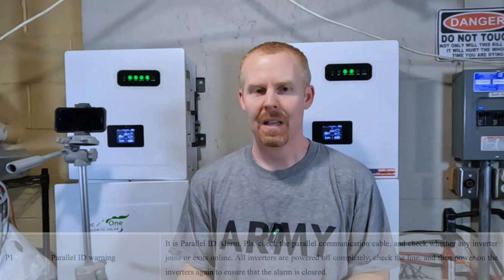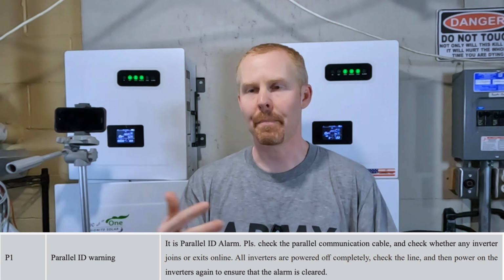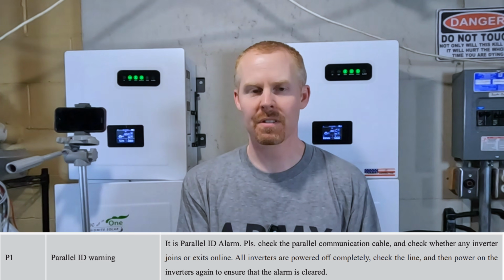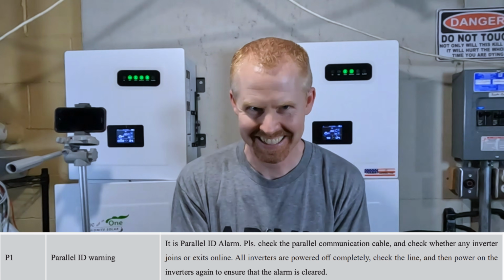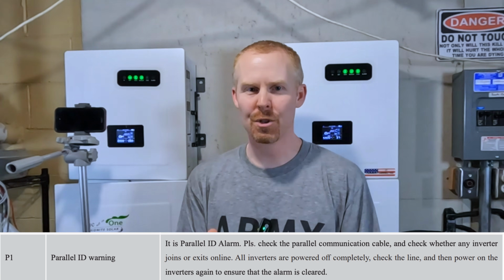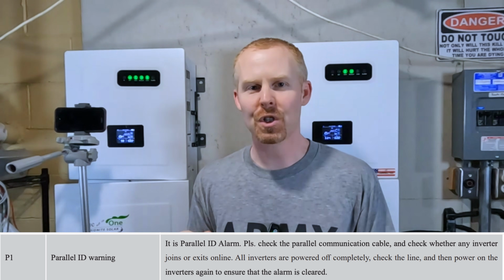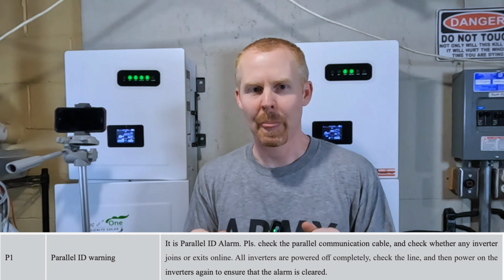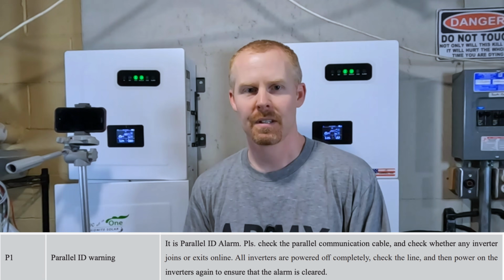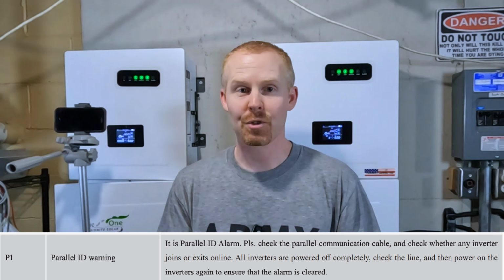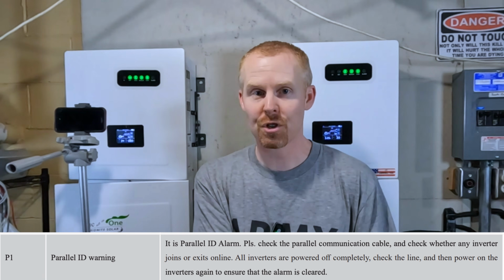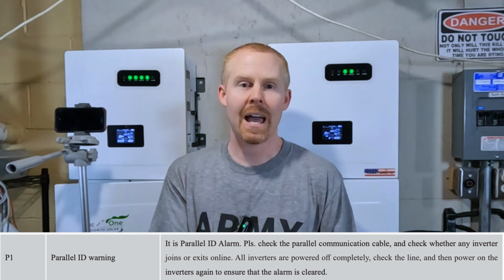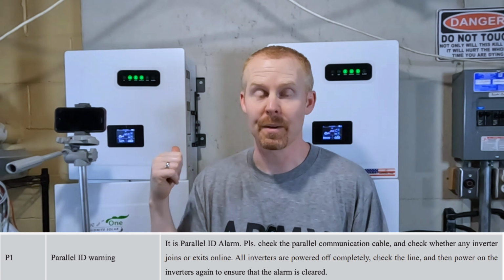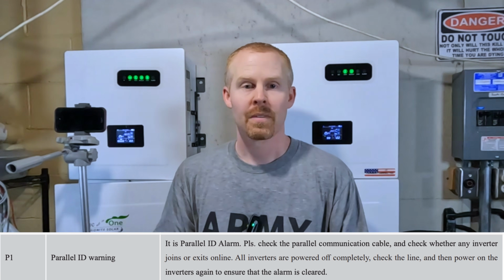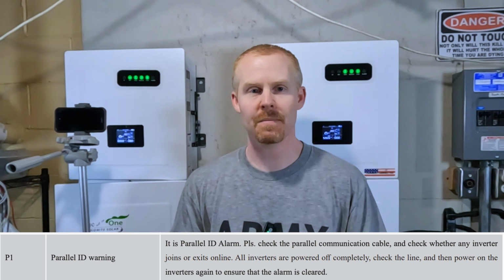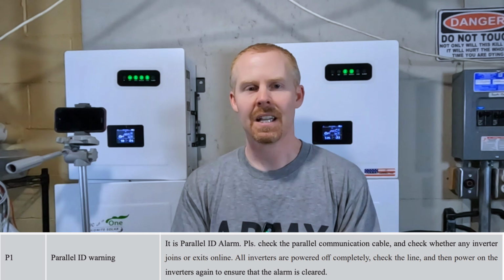So if you end up getting a P1 error, which is a paralleling ID error, I have gotten that several times, and every time it has been my fault. From what I've seen, usually that means that the inverters can't figure out which one is supposed to be the master because you have BMS communication plugged into both inverters. So if you unplug that from one inverter, so only one inverter has the CTs and has BMS communication, usually that error will go away. And usually what happens is one inverter starts up, the other inverter won't start up, and it just flashes that P1 error. So you'll have to unplug those cables out of the inverter that shouldn't have the communication, turn both of them off, and then turn them back on, and that should clear that error.